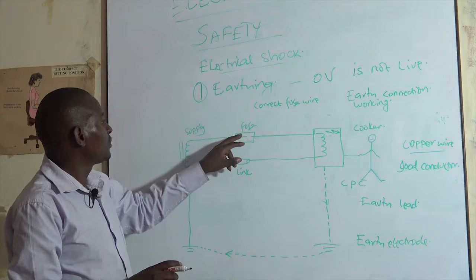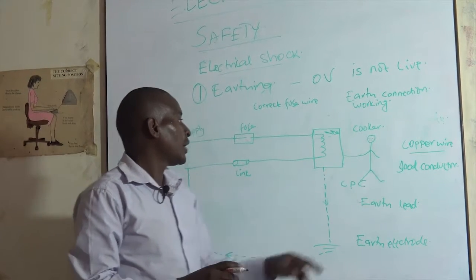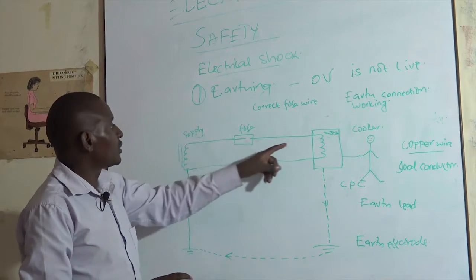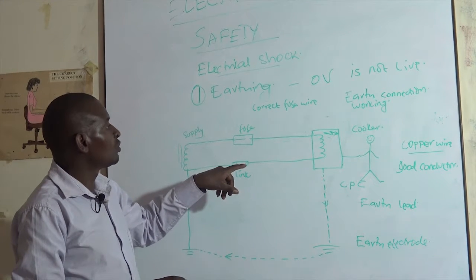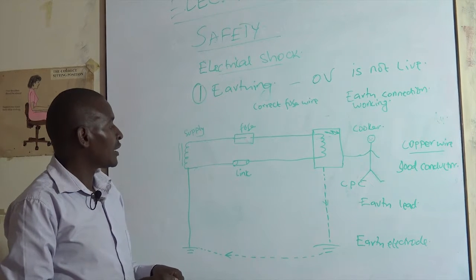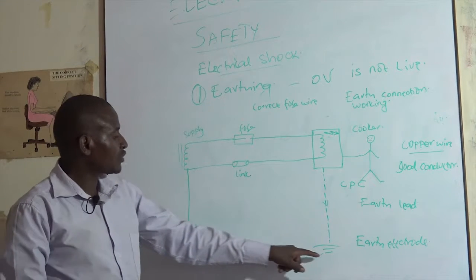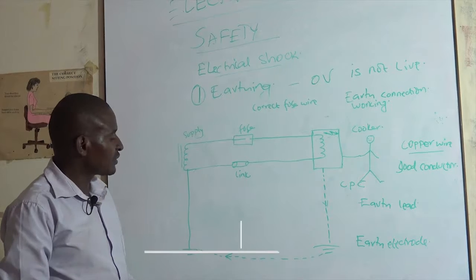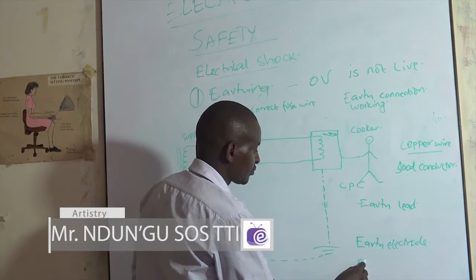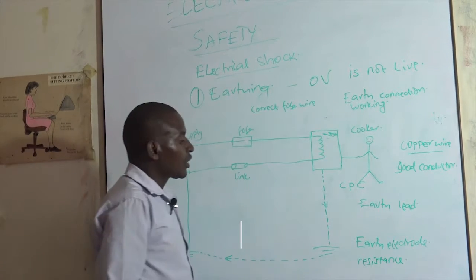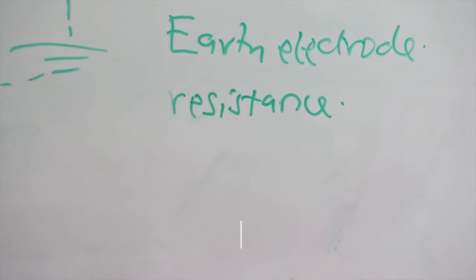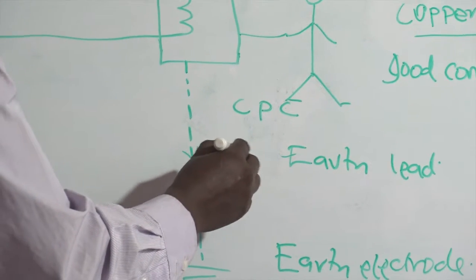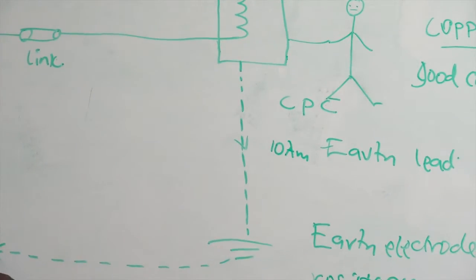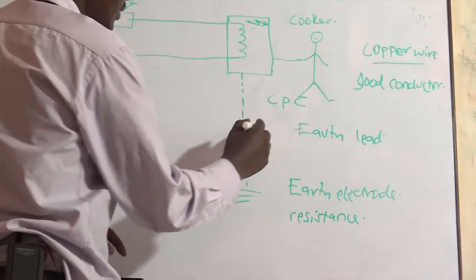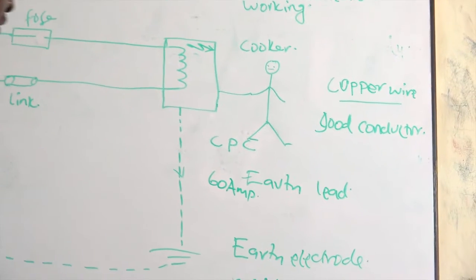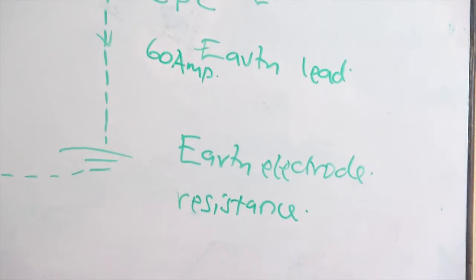Now, this is what would happen if you don't replace the fuse with a proper fuse. Probably you use a copper wire, and there is such a scenario. The current flowing will not be disconnected, because the fuse is not working. So chances are that in the process of current flowing, the earth electrode at the consumer level and at the authorities level, there might be some resistance. And because of this resistance, maybe you have a current of 10 amperes flowing, or let's say 50 amperes. Let's say 60 amperes.